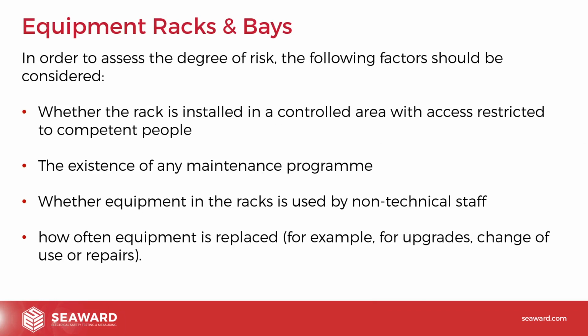In order to assess the degree of risk, the following factors should be considered: whether the rack is installed in a controlled area with access restricted to competent people, the existence of any maintenance program, whether the equipment in the racks is used by non-technical staff, and how often equipment is replaced, for example for upgrades, change of use or repairs.